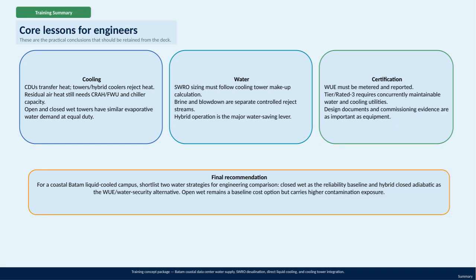Let's review the core lessons from our training focused on the Batam Coastal Data Center's water supply and cooling strategy. First, regarding cooling. Cooling distribution units transfer heat, while cooling towers or hybrid coolers are used to reject that heat. However, even after this process, there is still residual heat in the air that requires additional handling with CRAH units, fan wall units, and chiller capacity to maintain optimal temperatures. Interestingly, open and closed wet cooling towers have comparable evaporated water demands when operating at the same duty.